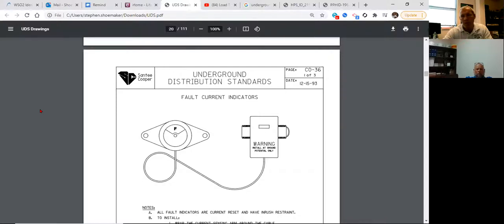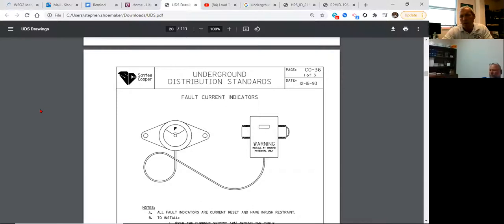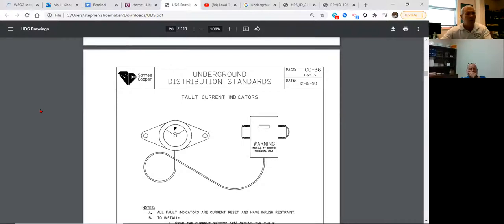Where did we start? What's your first indicator? The fuse. The fuse — that's your first indicator. We had to start right from the dip pole, test at the dip pole, then we went to the switch gear, tested at the switch gear, then we went to the cabinet, tested at the cabinet junction, then we went to the transformer. We were leapfrogging every single transformer using the high-pot adapters. Fault indicators are great tools. Remember, it's a tool — it doesn't work 100% all the time.